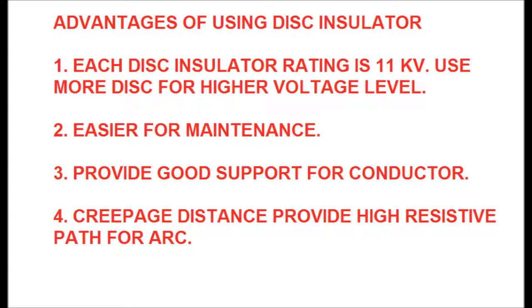Advantage two: it is easier for maintenance. If any disc out of 10 or 15 discs in a string fails, only the failed disc needs to be replaced and the other discs do not need to be changed. Advantage three: the disc insulator provides good support for the conductor in a transmission line.